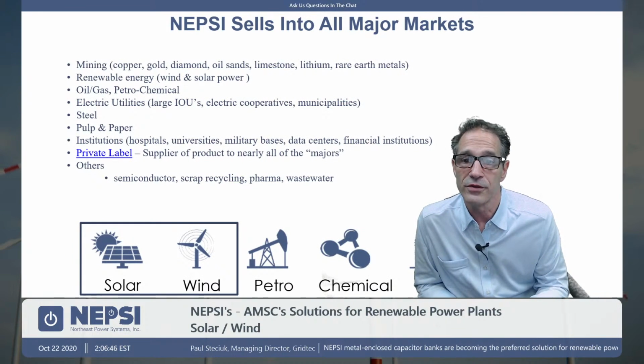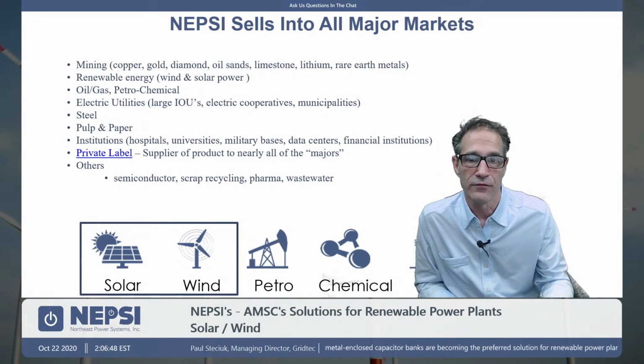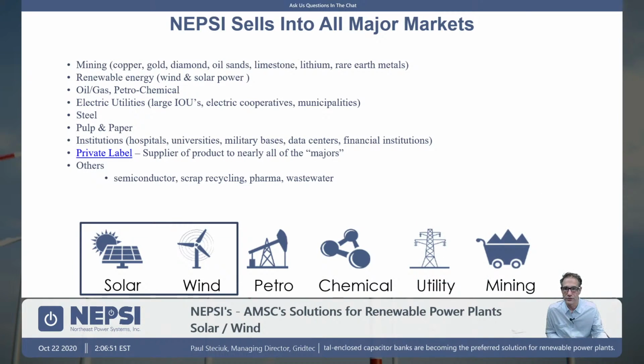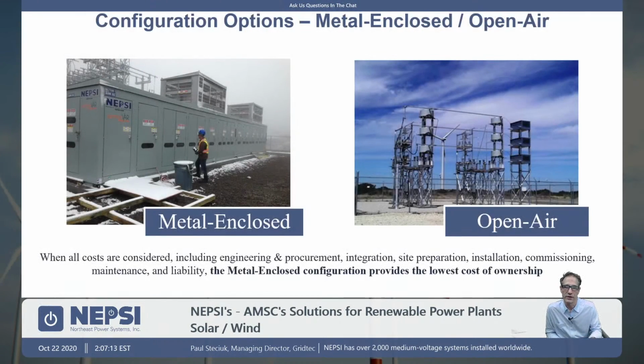So today's presentation, we're just talking about solar and wind. And don't forget, we sell into all the different industries: solar, wind, petrochemical, utility, mining. When you think about metal-enclosed systems, cap banks, filter banks, remember that the flavor of a capacitor bank or harmonic filter bank is going to change based upon the industry. So today we're talking about solar and wind, which is really dominated by 38 kV equipment, 34.5 kV equipment, and not typically 2.4 kV up through 25 kV. Typically it's almost always at 38 kV.